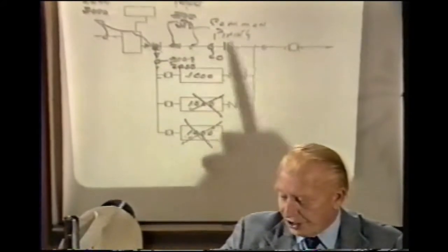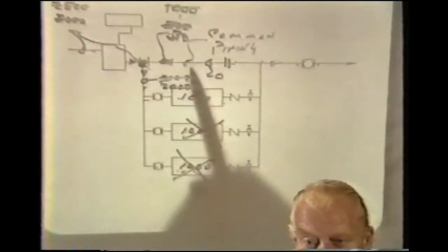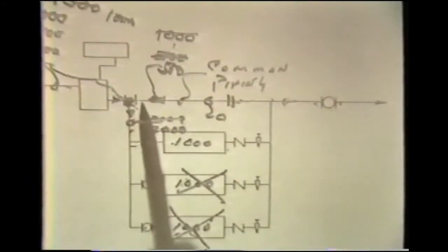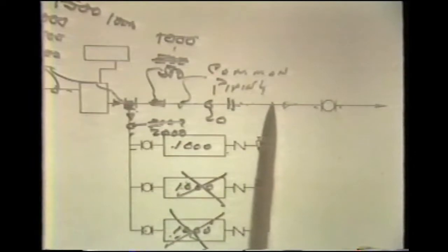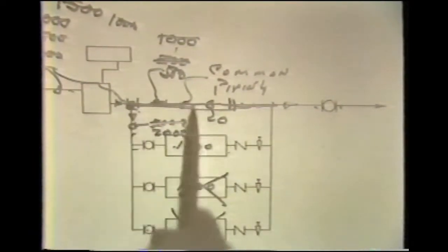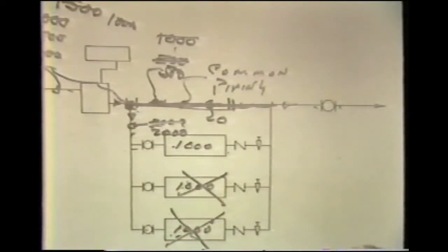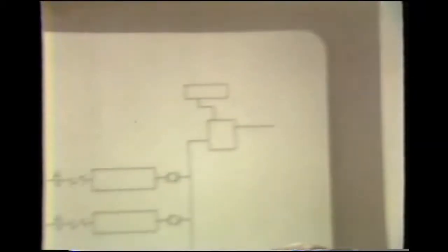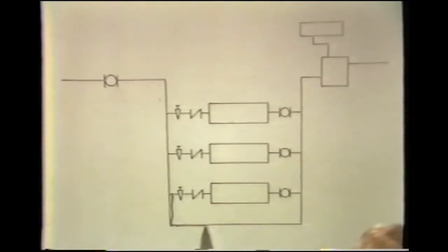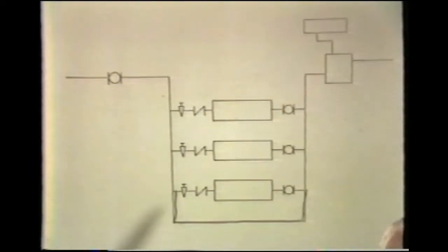Bill started out with a basic design correlated as illustrated here, but found through the contractor that there were great difficulties in putting the common piping in the location usually established for the classic position of common piping in distribution systems. So the contractor then proposed that the common piping be placed at the other side of the loop.